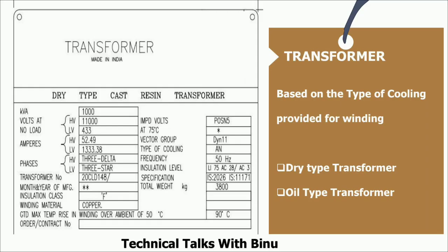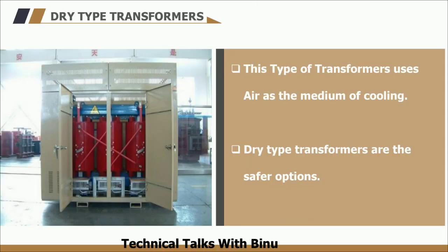This is the enlarged view of the nameplate and there you can see it is written as dry-type transformer. Now let's see in detail what is a dry-type transformer and what are the different classifications of transformers. Transformers are basically classified into two based on the medium of cooling used for the windings. These cooling mediums protect the transformer from getting heated up and prevent potential hazards. Based on this cooling method, transformers are classified into two: oil type transformers and dry-type transformers. In dry-type transformers, air is used as a medium of cooling. These are the safer option and we will be seeing them in most public places like a company or a building.